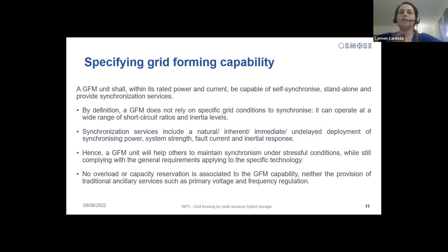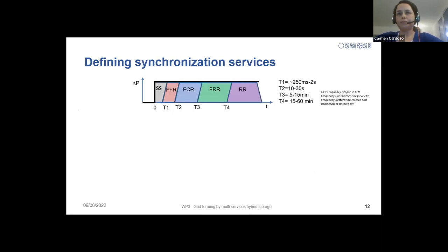And then for the synchronization service, there are many terms that are used, but the idea is that there is an undelayed deployment of active and reactive power or current for specific events. The main function of these services is to help other units remain synchronized, but not to provide frequency regulation. So we are not requesting overload capacity or capacity reservation with the grid forming capability, nor the provision of ancillary services.